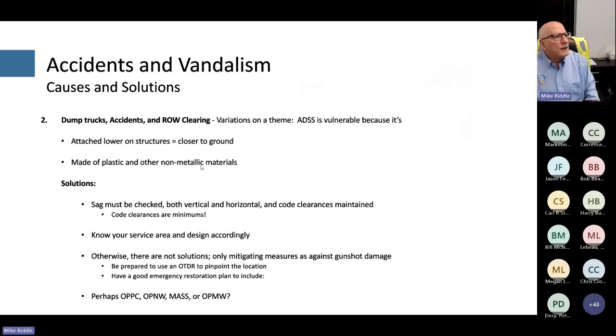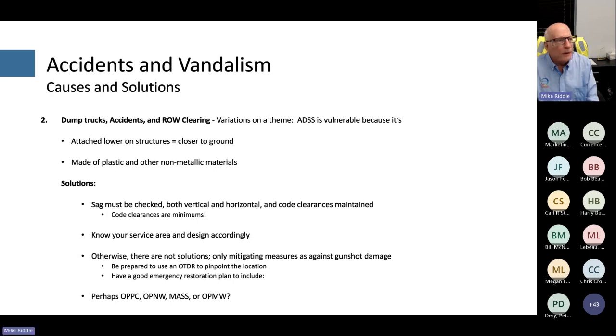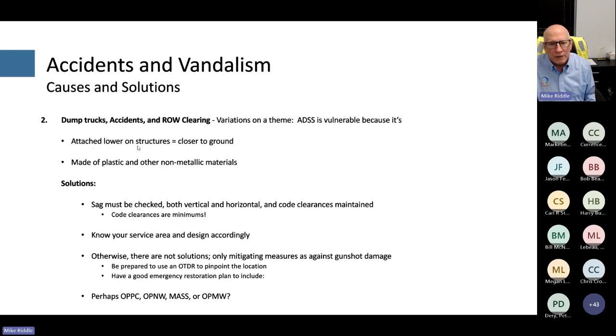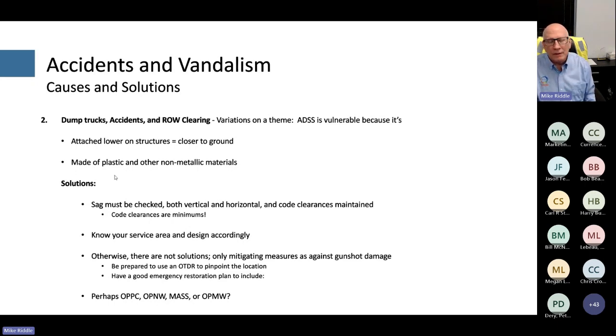Next in accidents and vandalism: dump trucks, right-of-way clearing equipment, and farm equipment can all clip or knock down ADSS cable. These share a common theme — ADSS is typically attached lower on a structure, below the phase conductors, making it closer to the ground and inherently more vulnerable to being struck. It doesn't help that it's made of non-metallic, dielectric materials.